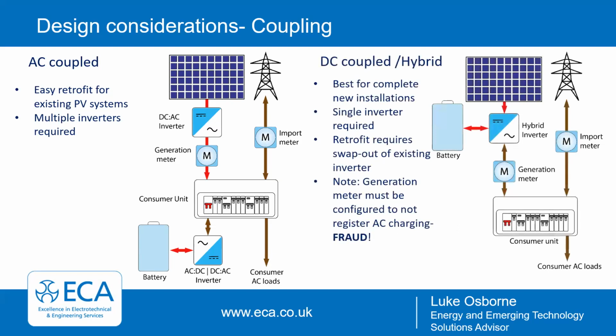But most of what installers will be doing as a complete system will be through a DC coupled or hybrid system, so you've just got one single inverter. It's all contained within that inverter - the battery is operating on DC, the solar panels provide DC, and you've just got one conversion before it goes to the consumer unit. So it saves the conversion losses that you would have from an AC coupled system.